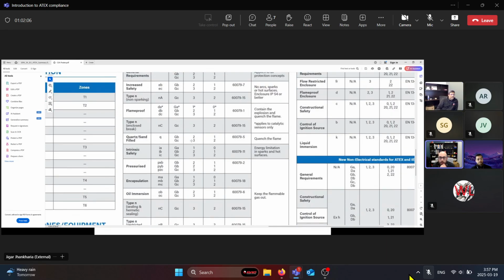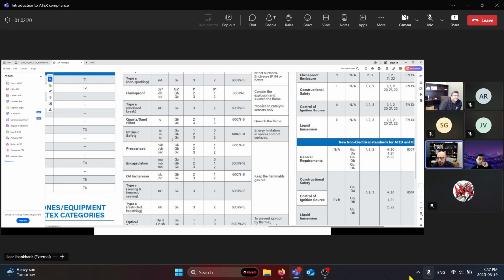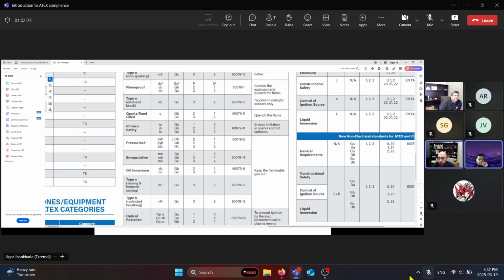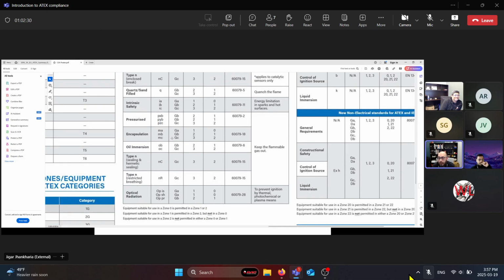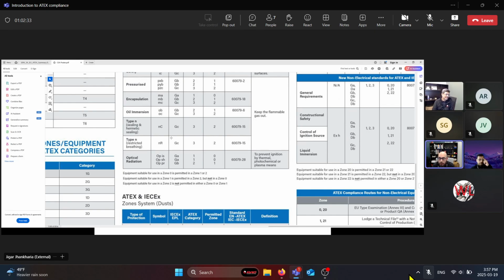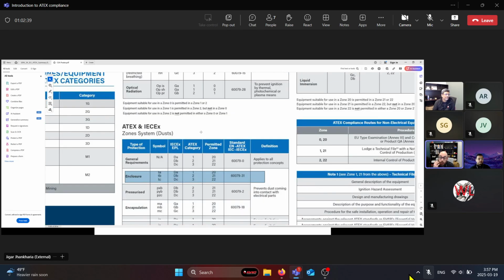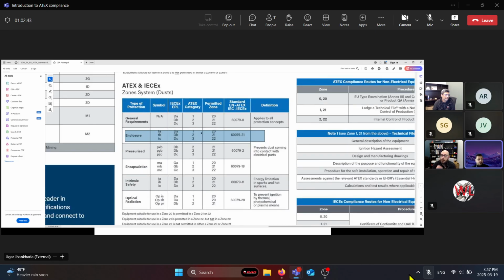Okay. And if memory serves, with intrinsic safety standards, when we say energy limitation, it's a very low voltage and current that the device is able to use. I'm not sure that's viable for our product, unless we really nerf the performance of it. Based on just pouring through it, I think it was a fraction of the current we use in our product. Yes, and that would mean you have to use intrinsically safe barriers and things like that in your product to nerf that as well. So encapsulation would be the better option in this case.